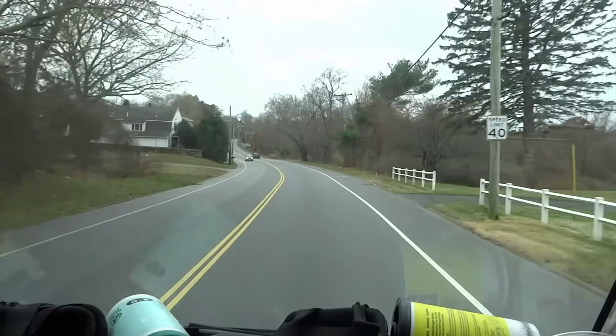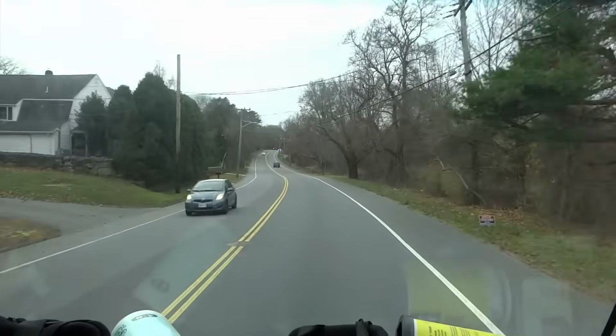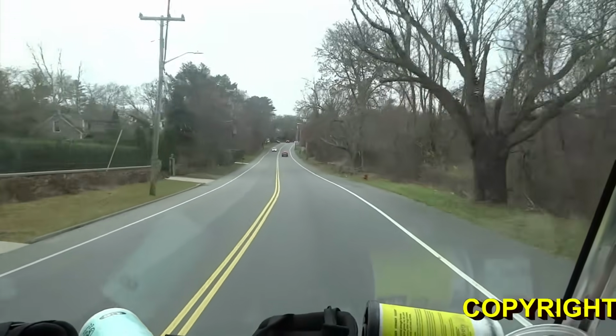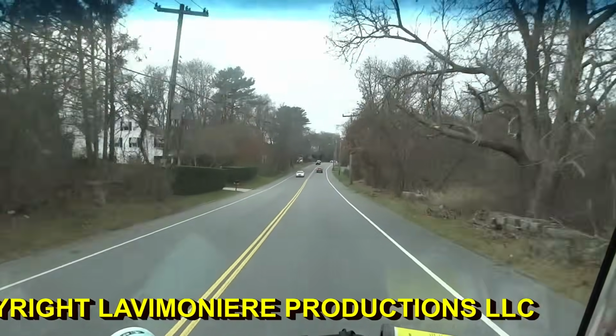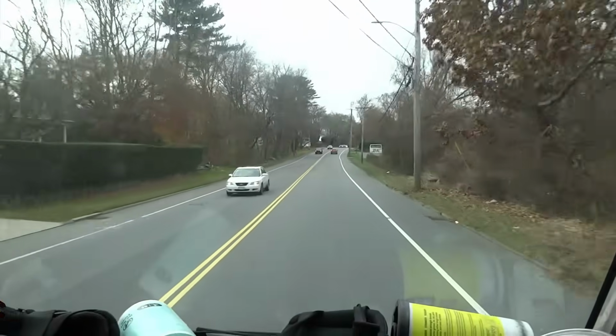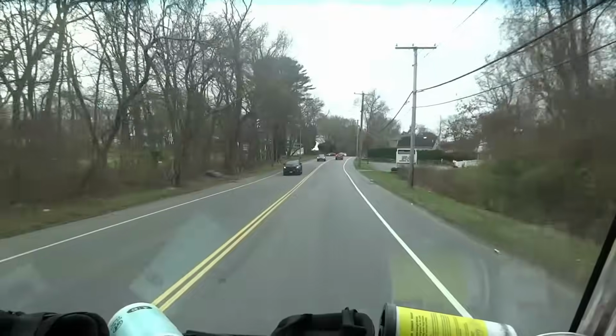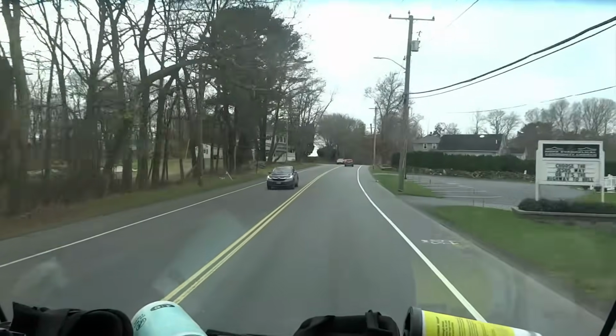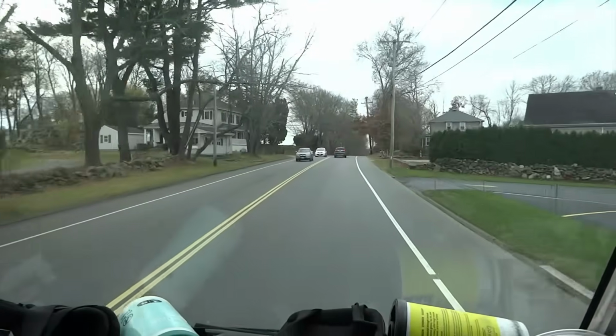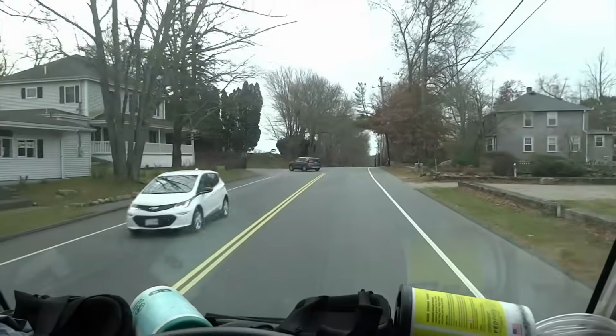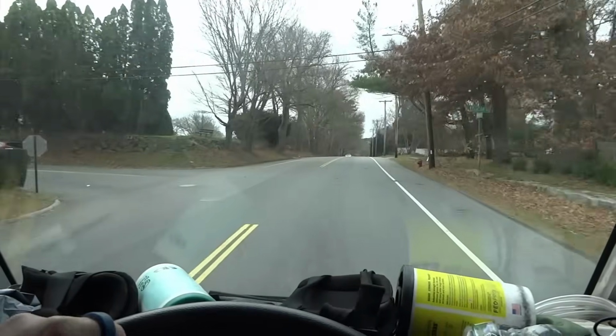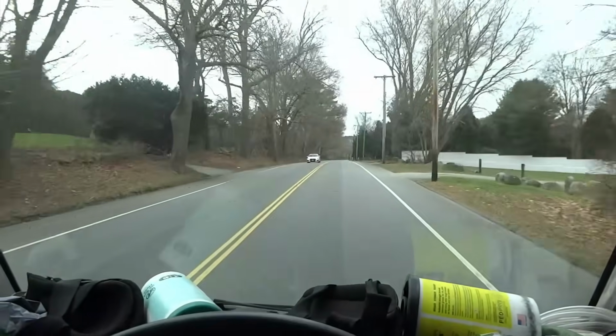Morning, guys. November 25th, 2025. You know, I got a call from a guy. I've been servicing his burner for a while. He's got an oil-fired Peerless boiler with a Roth tank outside. Two-pipe system coming into the house to a two-stage oil pump.